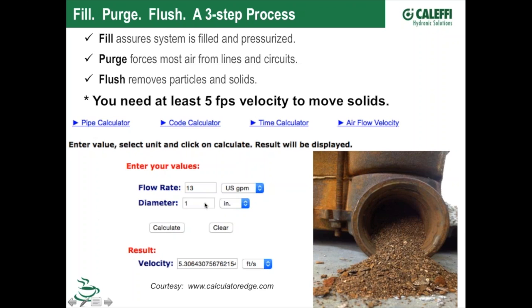Well, it depends on what pipes that you're trying to flush and purge through. And there's calculators. This is just one I pulled off a free online site here, that you can determine what the velocity is through a section of pipe. Here's an example. I put in 1-inch pipe ID, so that would typically be 1-inch copper, would have a 1-inch ID. At 13 gallon minute flow going through that, I'll get about 5 feet per second, and that's what I need to have to be able to scrub this type of debris out of a system, whether it's a new system for the first time or you're retrofitting an old iron pipe system. You might have some of this debris in there that you need to flush out.